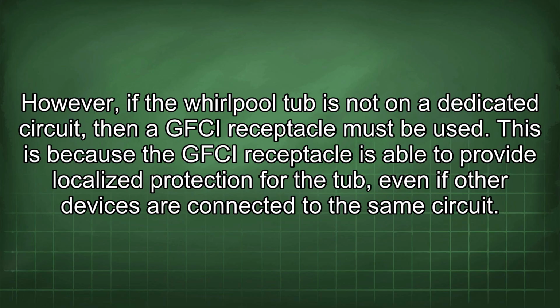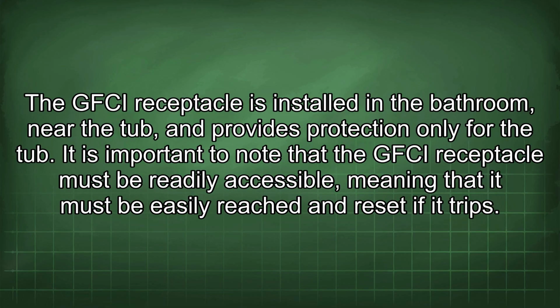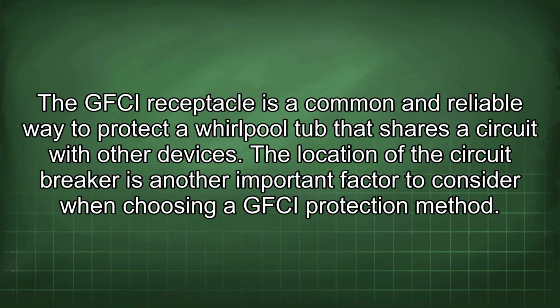The GFCI circuit breaker is installed in the main electrical panel and provides protection for the entire circuit. However, if the Whirlpool tub is not on a dedicated circuit, then a GFCI receptacle must be used. This is because the GFCI receptacle is able to provide localized protection for the tub, even if other devices are connected to the same circuit. The GFCI receptacle is installed in the bathroom near the tub and provides protection only for the tub. It is important to note that the GFCI receptacle must be readily accessible, meaning that it must be easily reached and reset if it trips.